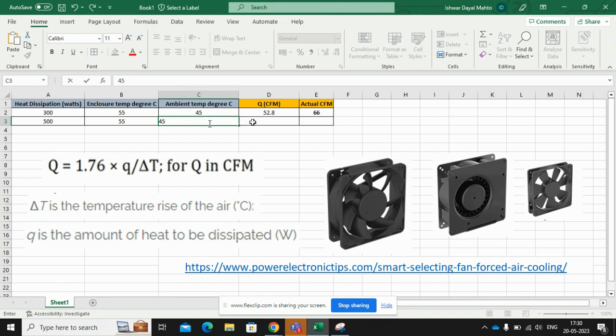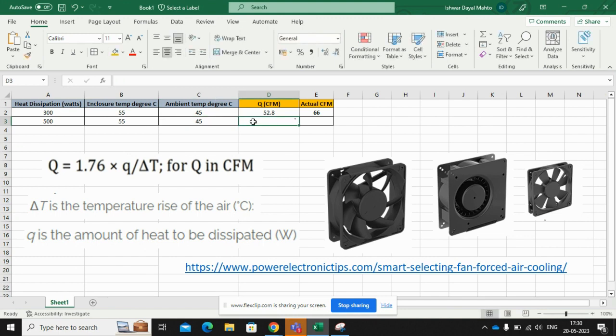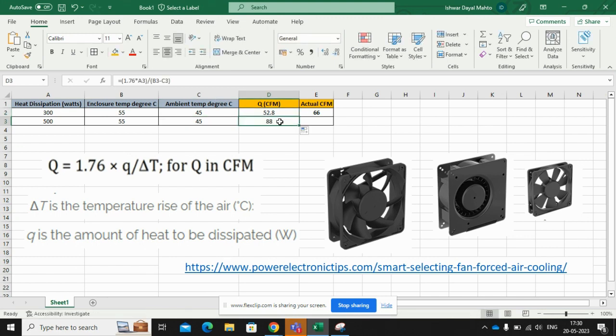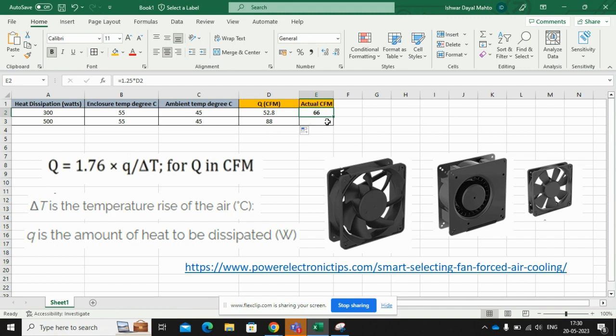Now I need to copy the formula. I am getting around CFM 88, and I need to take some margin around 25 percent. So I am getting my overall actual CFM of system is 110 CFM. So now how to approach to get your fan.